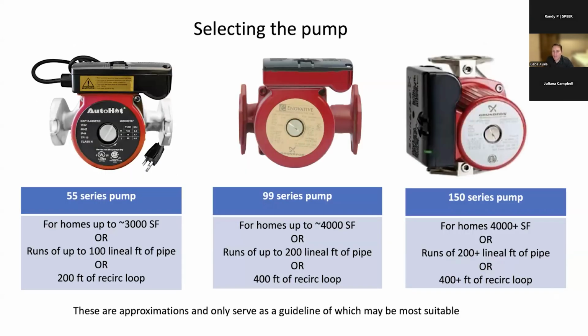We strongly recommend that you size the pump based on the application, based on the size of the house. It's not always one size pump fits all applications, especially for an on-demand system. So, we suggest that for homes up to about 3,500 square feet, you can get away with the smaller version pump.